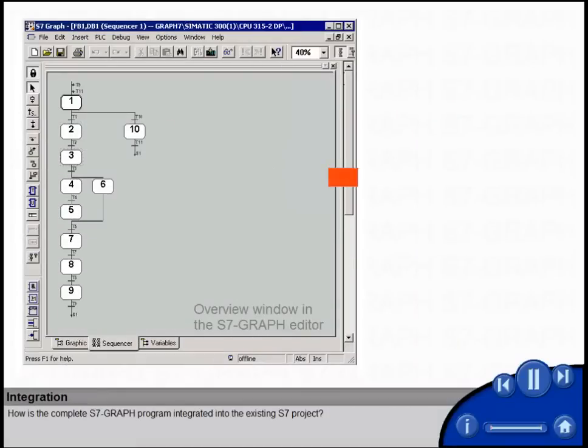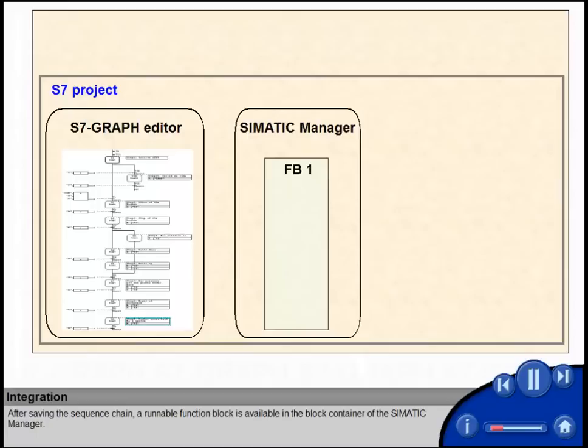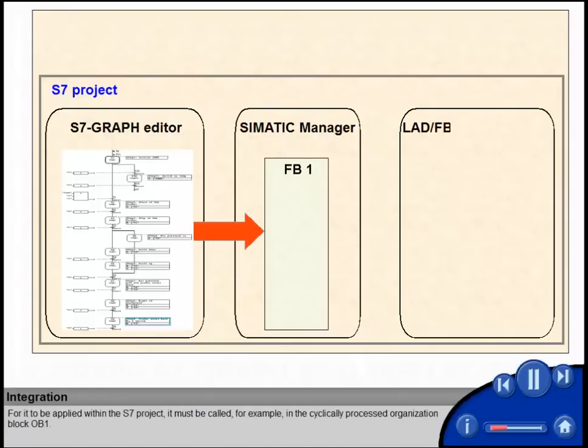How is the complete S7-GRAPH program integrated into the existing S7 project? After saving the sequence chain, a runnable function block is available in the block container of the SIMATIC Manager. For it to be applied within the S7 project, it must be called, for example, in the cyclically processed organization block OB1.